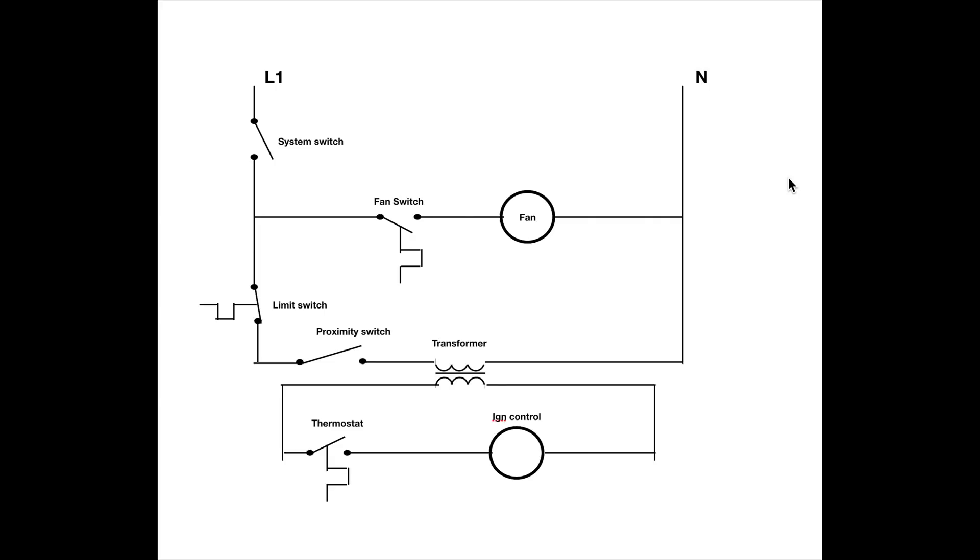Okay, this is a schematic diagram, kind of a simple one. System switch is here, that's just a manual on-off switch. I'll show it to you out on the unit heater also but I'm gonna go through the schematic here right now. Then you have a heat operated fan switch right here and a fan motor. So when the heat exchanger heats up, it's gonna close that and turn it on.